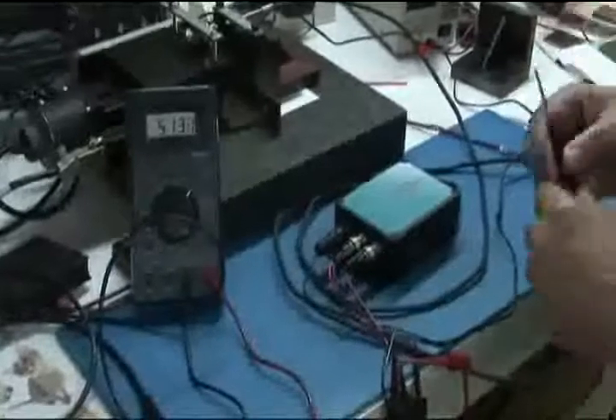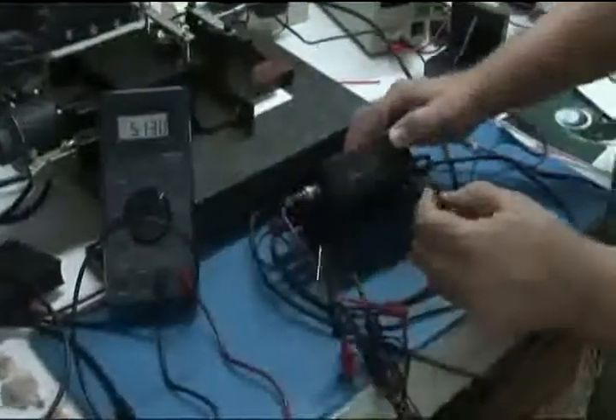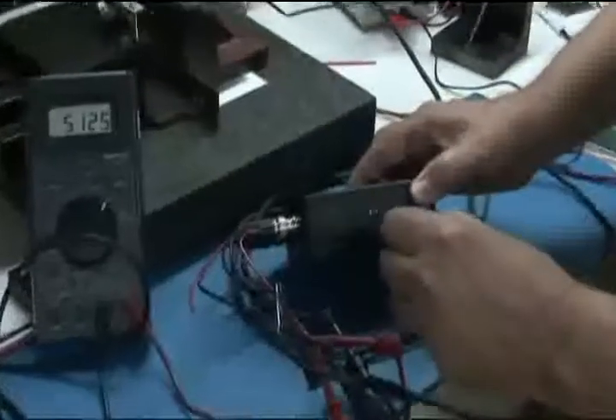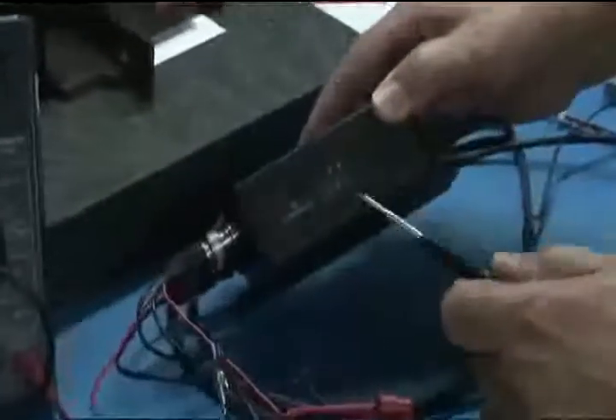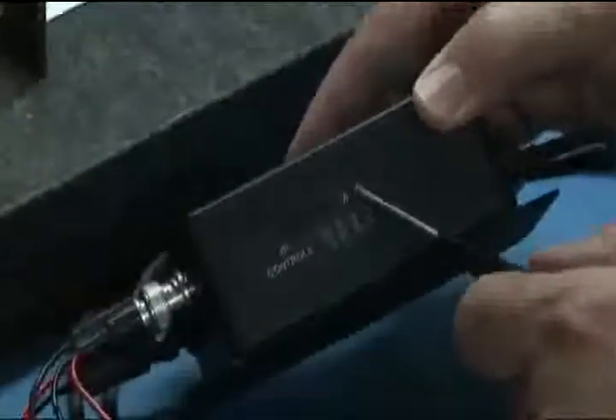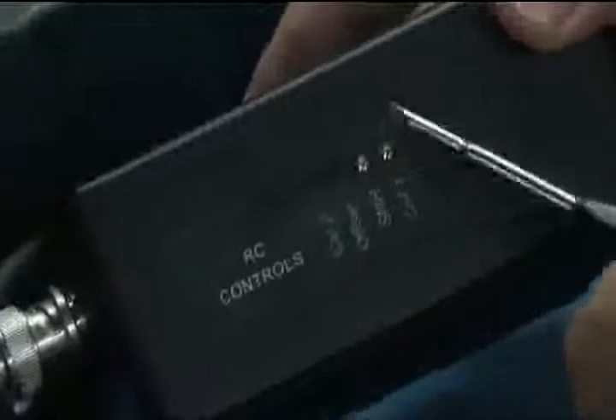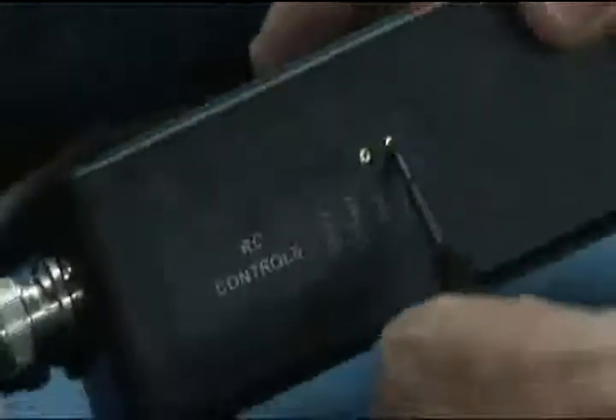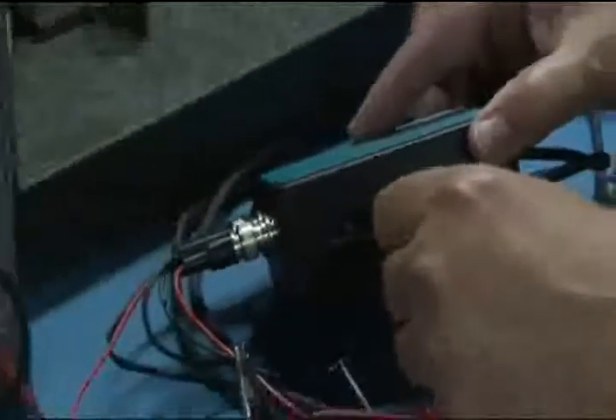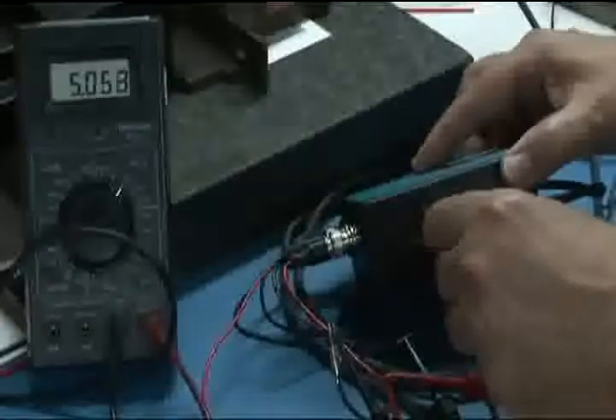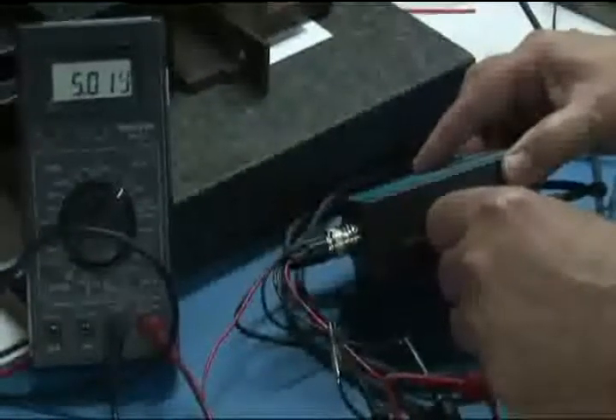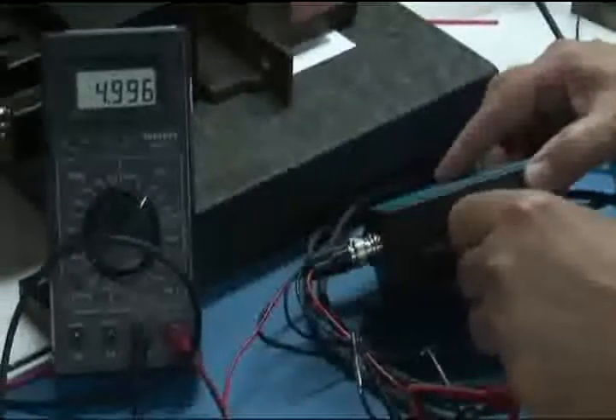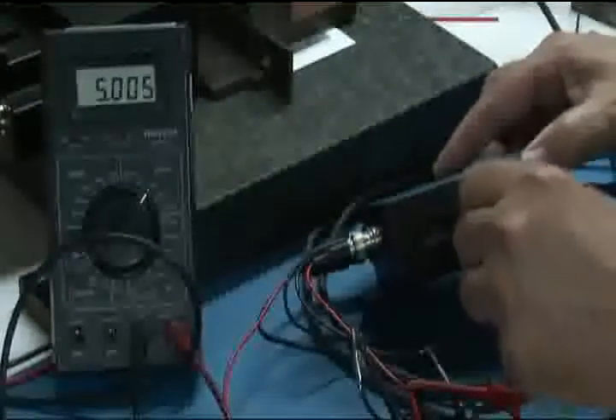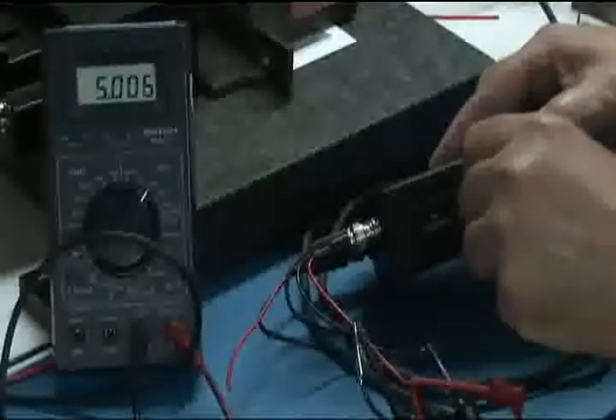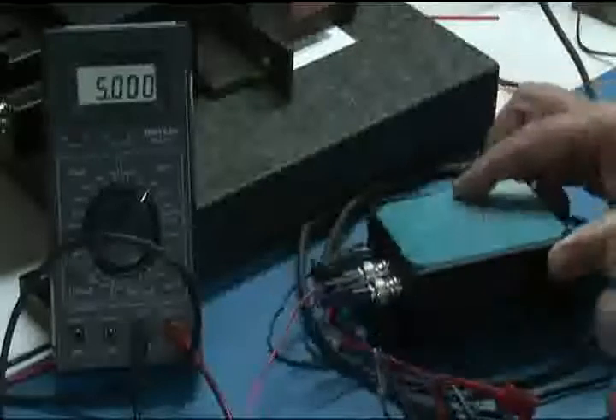So what you want to do with every sensor that you set up in your chambers is get to this CAL1 control, and on the sensors we've delivered to you, this CAL1 control may be blocked off. If it is, you just need to lift this label up and get underneath it, and you'll get to this little trim pot. And we're going to set this output to as close to 5 volts as we can get it. And so let's say that's about as good as we're going to do here. All right, hey, I did pretty good.